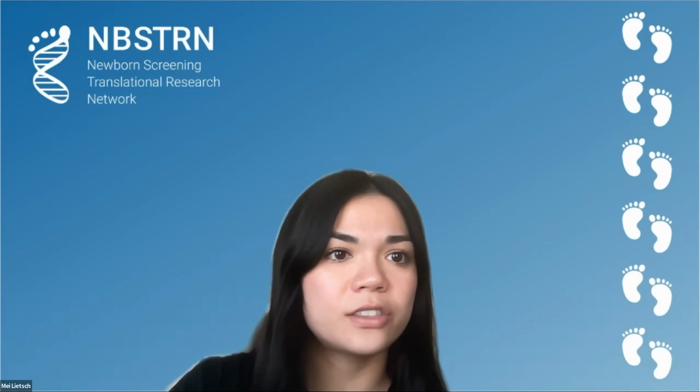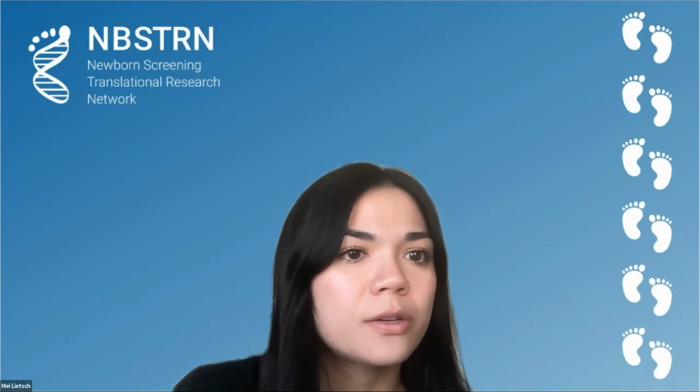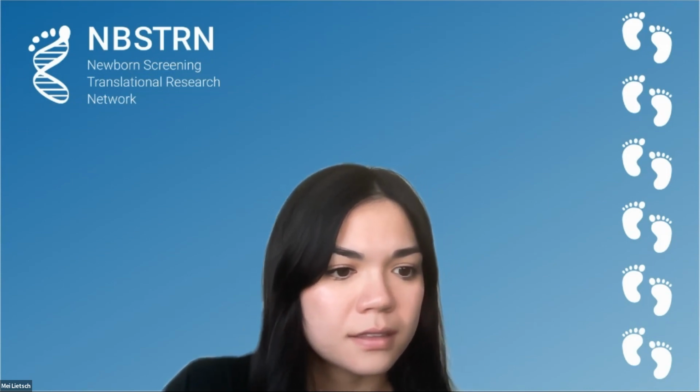It looks like we have a question in the chat from Joe. He asked, can the mass specs currently used in newborn screening programs be used for this assay? So we do use a more sensitive instrument for this because the peptides are in such low concentration. I guess we haven't tested specifically whatever different instruments all the newborn screening labs have around the country. But my suspicion is that a more sensitive instrument is going to be needed. So we're working with instrument manufacturers to try and partner with them to make it easier. But it's a good question because it's an important point. We use a Xevo TQ-XS, which is a slightly more sensitive instrument.